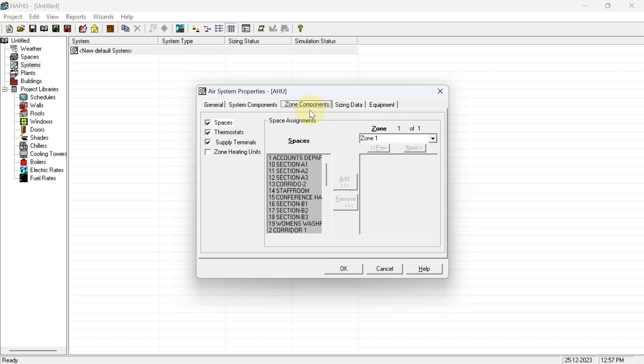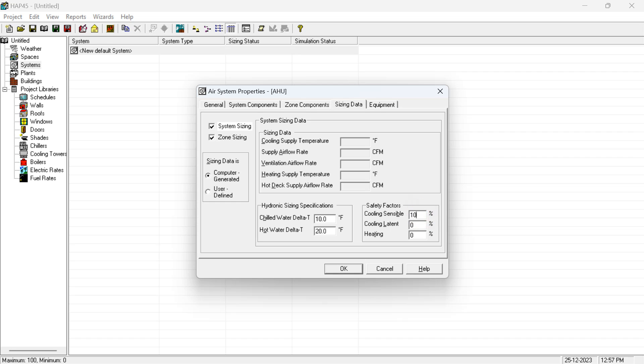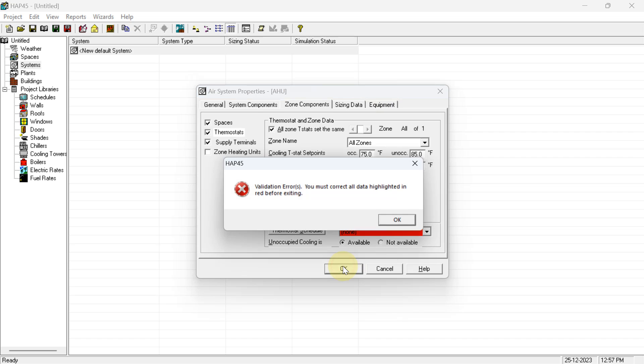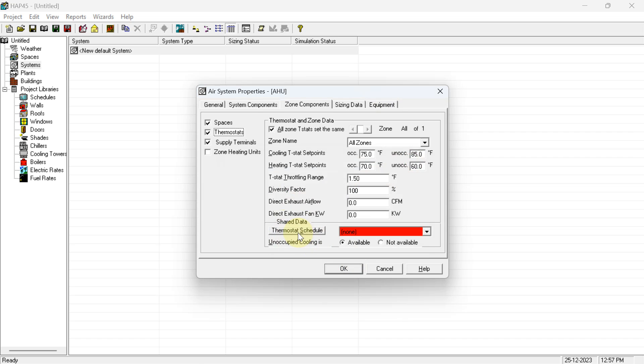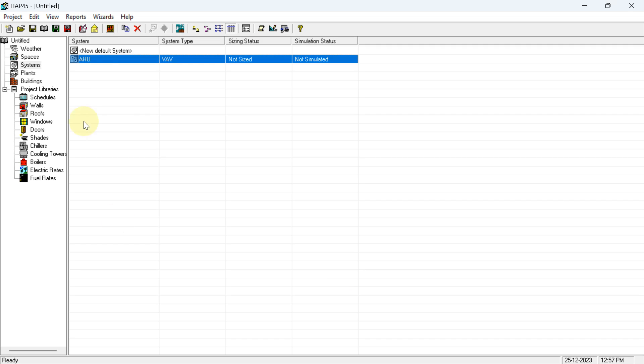In Zone Component, write VAV-1 and select the room — account department. In Sizing Data, apply a 10% safety factor for cooling sensible, cooling latent, and heating if required. No input is needed in Equipment. Hit OK. One error appears — we need to create a thermostat schedule. Create a schedule named 'Thermostat' with schedule type Fan or Thermostat. Hit OK.